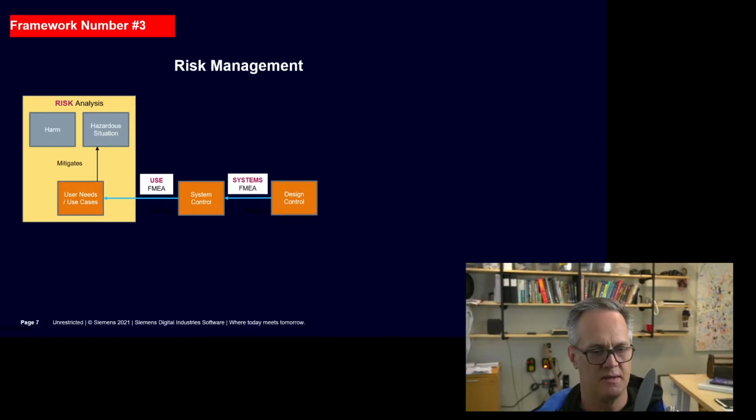into our process. Now, those design controls, I'll just give you a couple examples, would be maybe that the sterile barrier bag will not allow for ingress of harmful bacteria. Okay, so that's the design control that we're going to use.